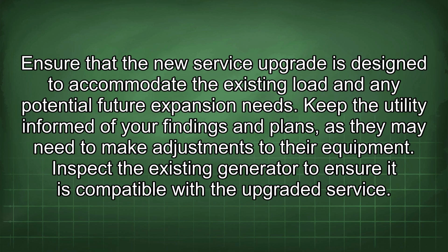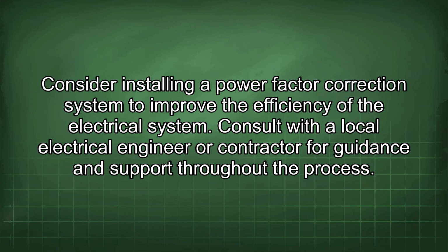Ensure that the new service upgrade is designed to accommodate the existing load and any potential future expansion needs. Keep the utility informed of your findings and plans, as they may need to make adjustments to their equipment. Inspect the existing generator to ensure it is compatible with the upgraded service. Consider installing a power factor correction system to improve the efficiency of the electrical system. Consult with a local electrical engineer or contractor for guidance and support throughout the process.